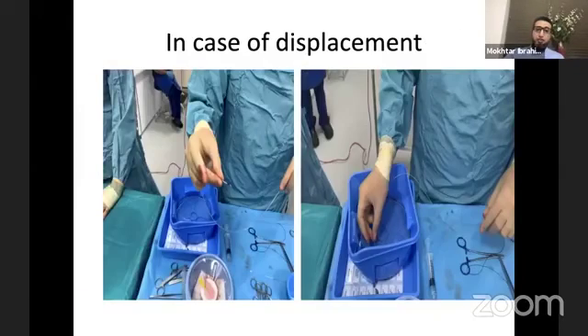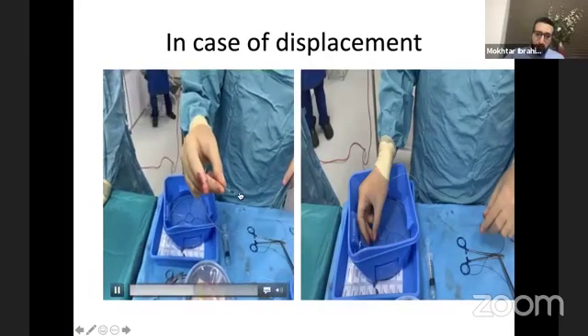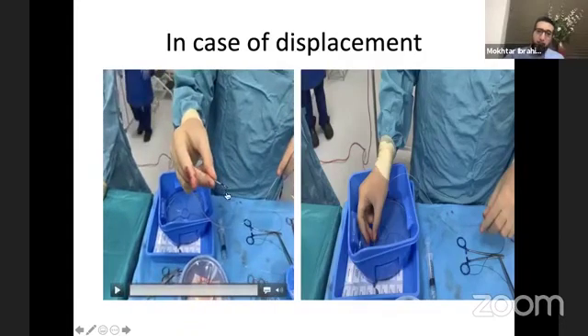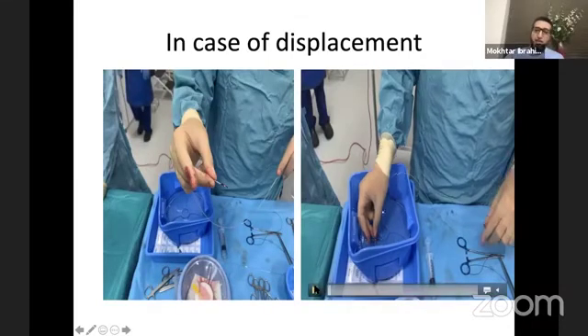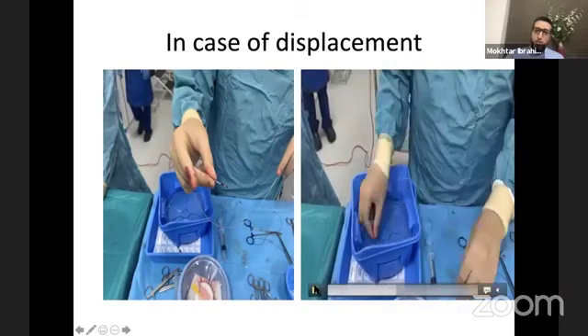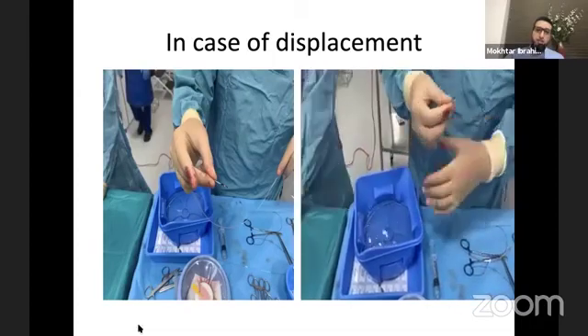Importantly, if your lead displaced, try not to reposition it immediately. Have a look at the lead, because what we found is sometimes after the first placement, you get blood clots or tissues, myocardial tissues on your lead. And if you try to reposition it back and screw it, it's either not fixed in position or you can't pace from it. So give it a good cleaning, good wash before trying to reposition it again.